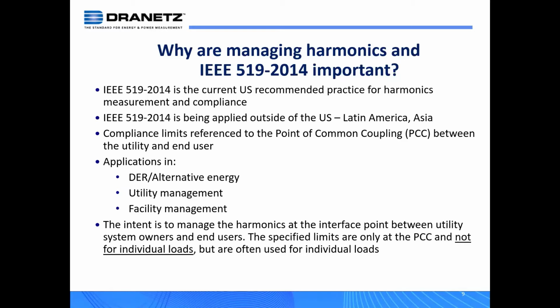However, a lot of applications take that into the facility and use these types of measurements at the terminals of a motor or a process or something like that. So again, it's only required and the standards are set up at that point of common coupling, but the owners of our products and the users of this recommended practice use it throughout facilities, typically.